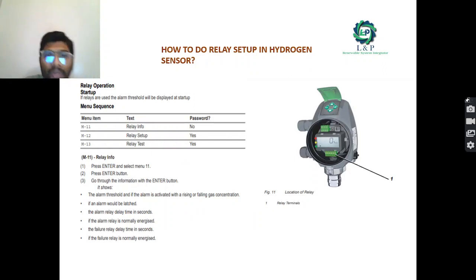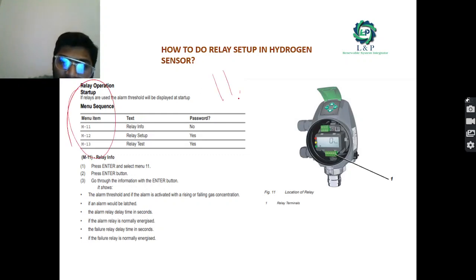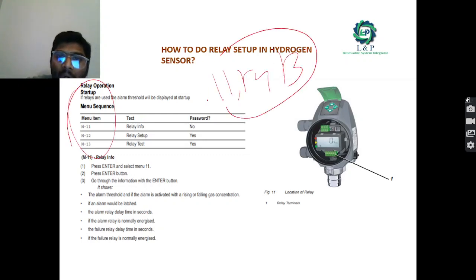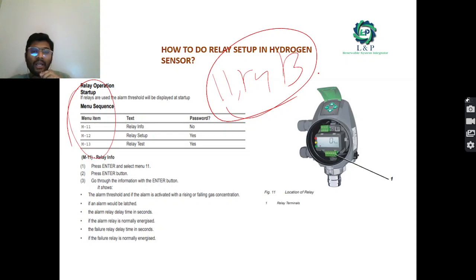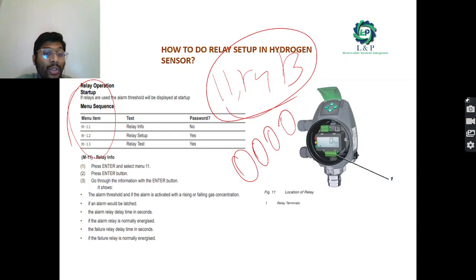Okay, in order to get into it, we have three menus available: menu 11, menu 12, and menu 13 are for the relay operations. If you get into menu 11 using the enter button, it is only to know the relay information, what sort of relays are available. If you go for menu 12, you can do the relay setups. For that, you need the same password, 0000. And if you want to do the relay test, you can go into menu 13.